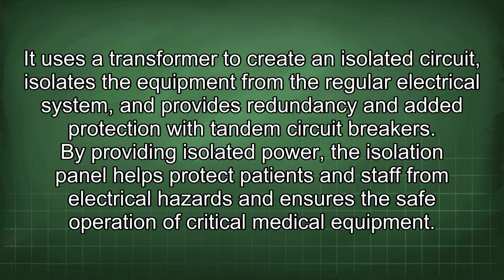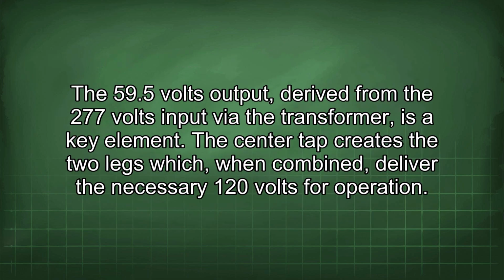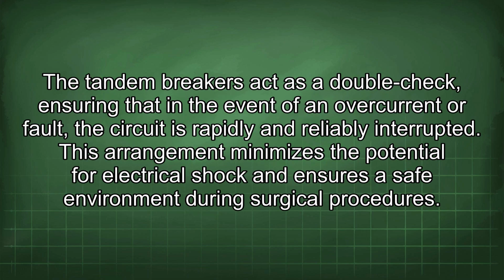of critical medical equipment. The 59.5 volts output derived from the 277 volts input via the transformer is a key element. The center tap creates the two legs which, when combined, deliver the necessary 120 volts for operation. The tandem breakers act as a double check, ensuring that in the event of an overcurrent or fault, the circuit is rapidly and reliably interrupted. This arrangement minimizes the potential for electrical shock and ensures a safe environment during surgical procedures.